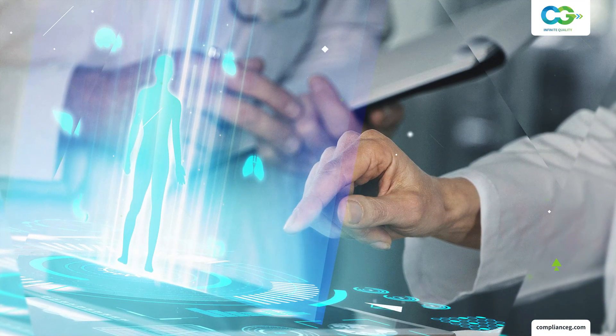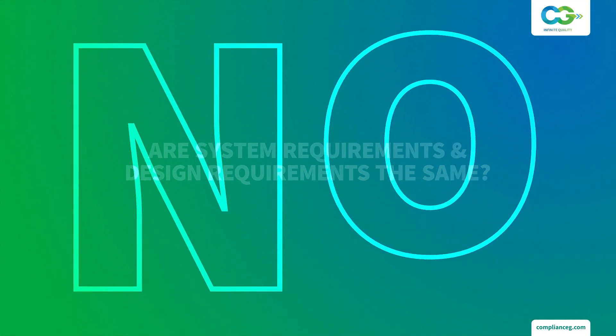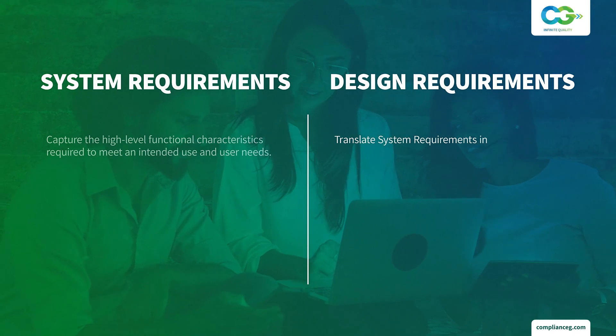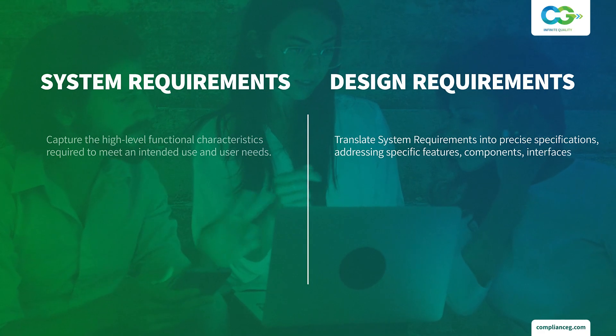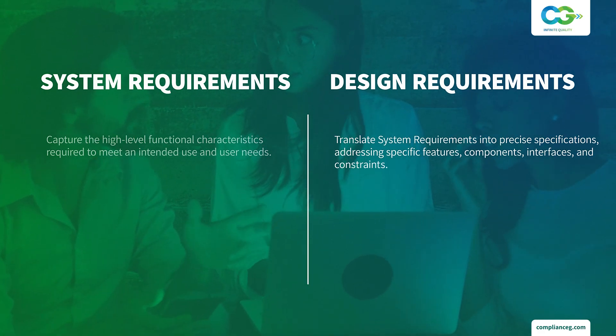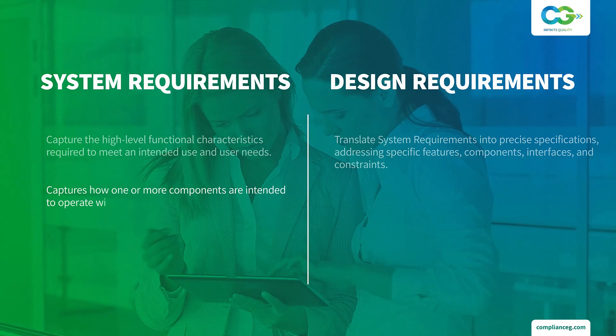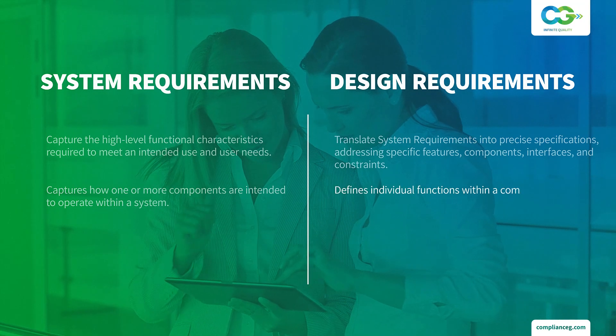Are system requirements and design requirements the same? No. System requirements capture the high-level functional characteristics required to meet an intended use and user needs. Design requirements translate system requirements into precise specifications addressing specific features, components, interfaces, and constraints. A system requirement also captures how one or more components are intended to operate within a system, while a design requirement defines individual functions within a component.